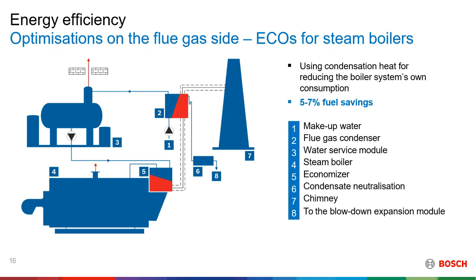Apart from the normal economizer, there is a second economizer called a condensing economizer. As you can see on the setup, we have the boiler itself, then the normal economizer, number 5, then a condensing economizer, and two other new accessories. Number 6 is the condensate neutralizer. Number 8 is a pipe, ideally going to a blowdown expansion module or drain.